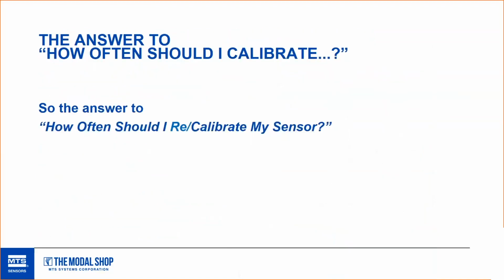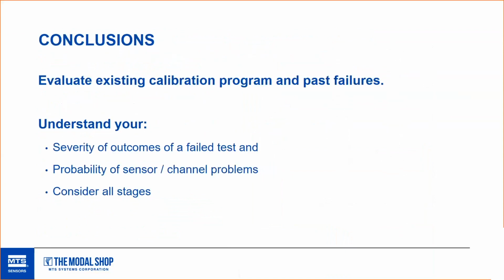So really, we're just wrapping up here. The answer to how often you should calibrate is really still, it depends. It kind of is on you. To conclude, really, evaluate your existing cal program. Make sure you're aware of any time that your cal program didn't work for you. Start to keep track of those. Make a KPI or metric in some way internally, so you could say, well, remember that time when this happened. What can you do differently to avoid that risk?